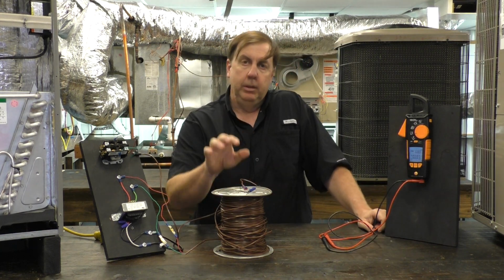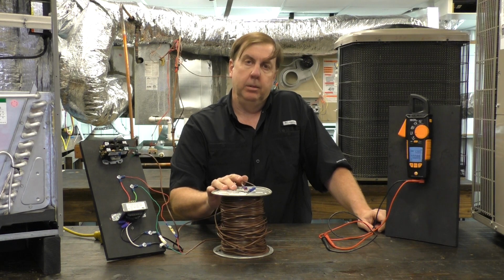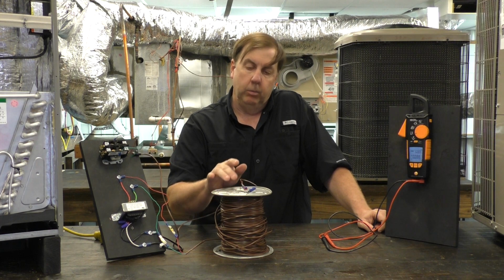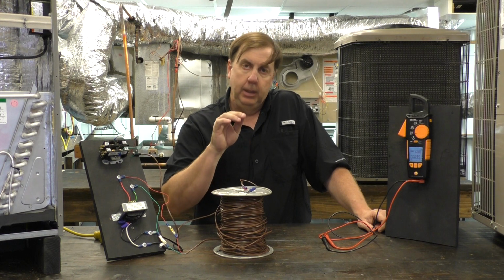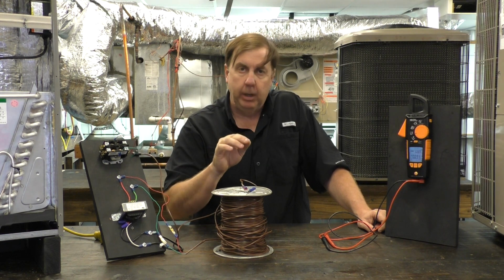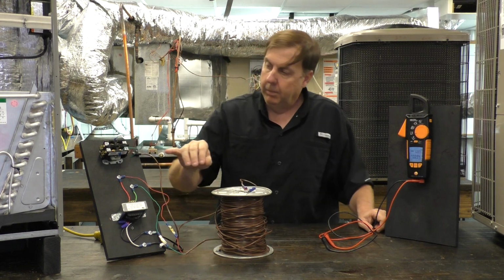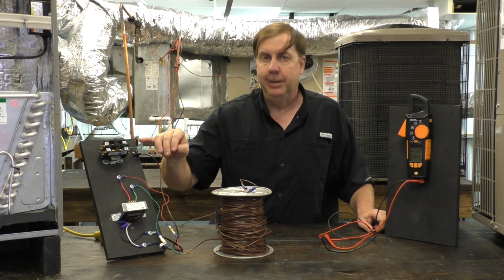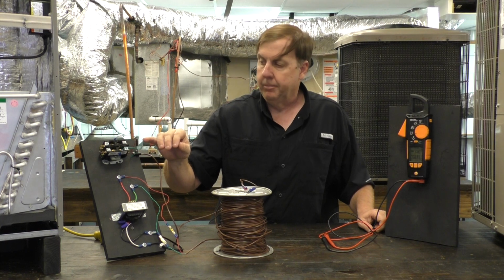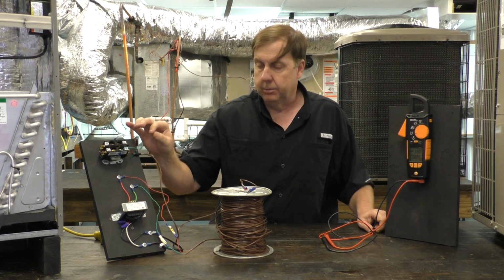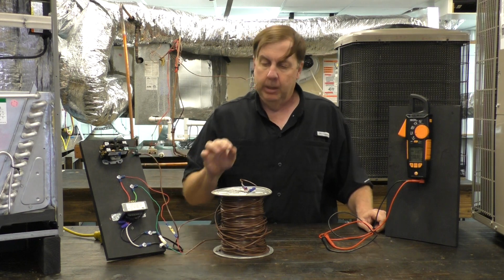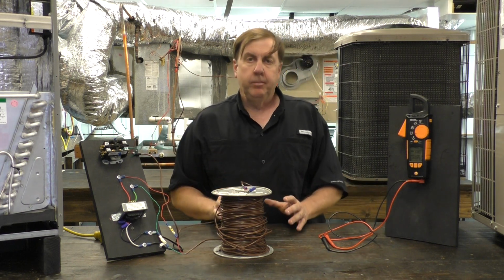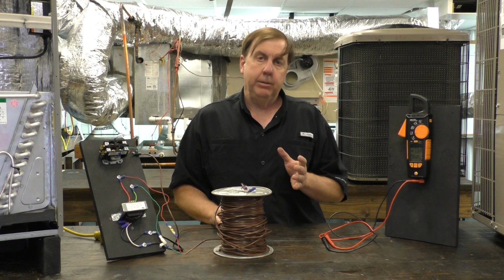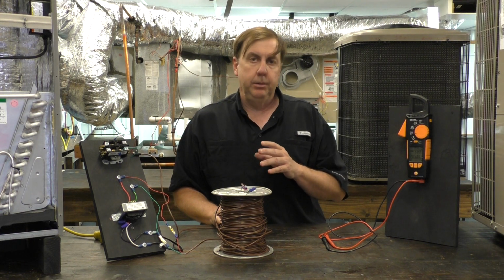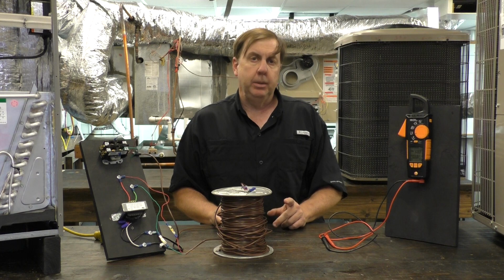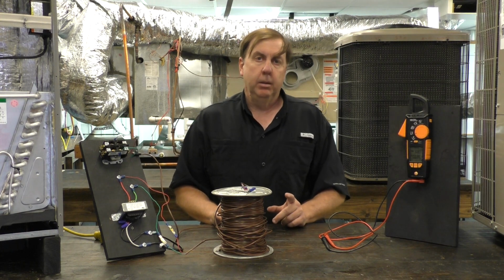If we have the smaller wire, which is very typical, the 24 gauge wire, and we were to run a drop like this, say from the attic to the thermostat and to behind the garage where the condenser might be, we might get a voltage at our contactor of 19 volts. Seen this many times. If that occurs, the voltage is going to drop to the point the contactor is going to chatter. So voltage drop is a real thing. Always measure your voltage not only at the transformer, but at the contactor, so you can determine if it's a factor in possibly either causing your transformer to burn out or not pull in altogether.